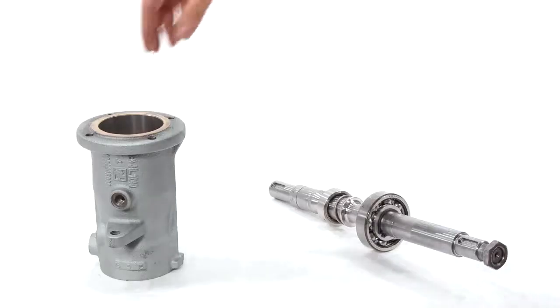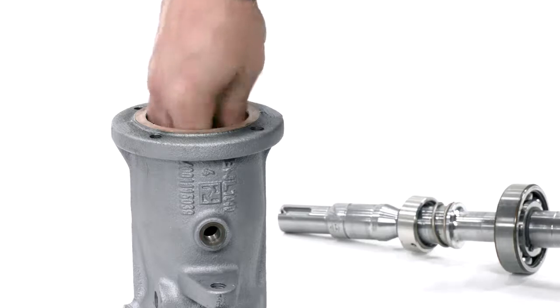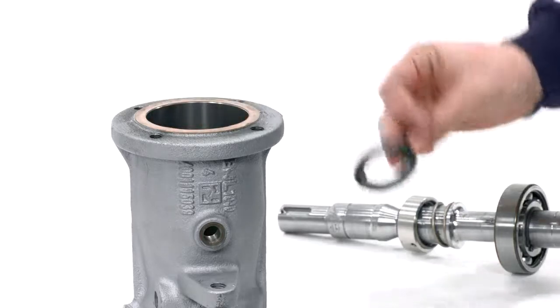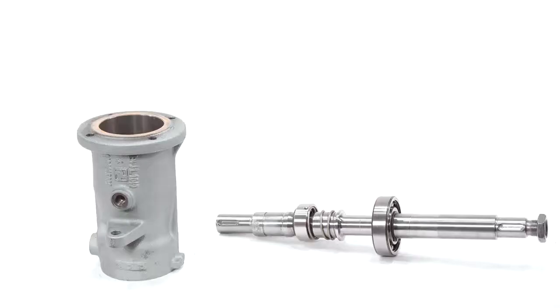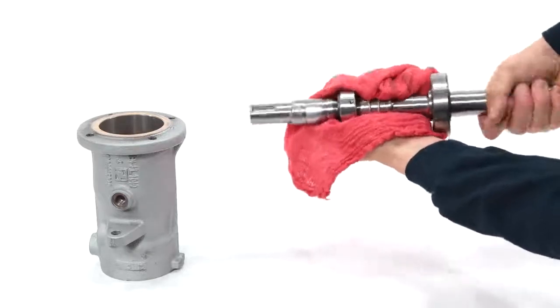Carefully remove the mechanical seal stationary face and o-ring from the bearing housing. Twist the rotating assembly to help remove it from the exposed pump shaft.